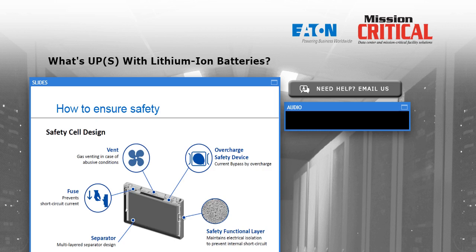So how do we make sure that these batteries are safe? These batteries are a lot bigger than the one in your phone and the one in your laptop or your hoverboard. So what is being done to make sure that this battery never gets into a mode where it tries to get warmer than its ability to dissipate heat? Well, first thing you see is a vent. Now, this is not a fan in spite of the icon. It's a similar vent to what you might find on a valve-regulated lead-acid battery. If the battery is abused or overcharged, for example, the vent will open up and let out the internal pressure.